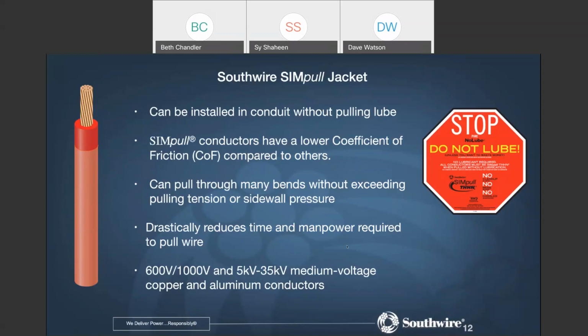Just very quickly about that. The NEC does have a requirement that for 360 degrees of bends you would need to install a pull box. And you still need to comply with the NEC in regards to that. But the use of Sim-Pull products in many, many instances would allow you to do a straight pull through at that box rather than having to pull the conductors out and then pull them back in again.